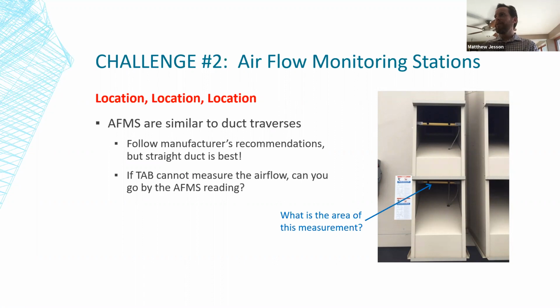So let's take a look at this particular installation. I'm going to say out-of-state engineer, out-of-state contractor. But these are on the outdoor air intake of a rooftop. And we talked about area and velocity. First of all, what's the area in that cross section where that airflow station is located? It's a sloping duct, right, coming right off the intake. And I would imagine that airflow is going to be very turbulent there. Are those two velocity readings in that station on each one positioned just right to get the average velocity? It's a little hard for me to believe that they are. Also, you might note that those look pretty exposed to the weather. And in fact, in this particular case, they got flooded and failed. So you've got to be careful as to where you put them.